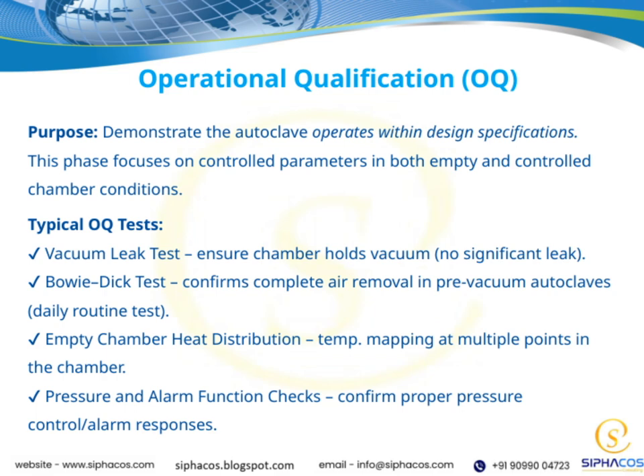Now, some of the typical tests we perform during OQ include the vacuum leak test. This test is essential because it confirms that the chamber can hold a vacuum without any significant leaks, which is vital for effective sterilization. Another important test is the Bowie-Dick test. This routine daily check verifies that the autoclave can properly remove air from the chamber, especially in pre-vacuum models, ensuring that sterilization conditions are uniform throughout.